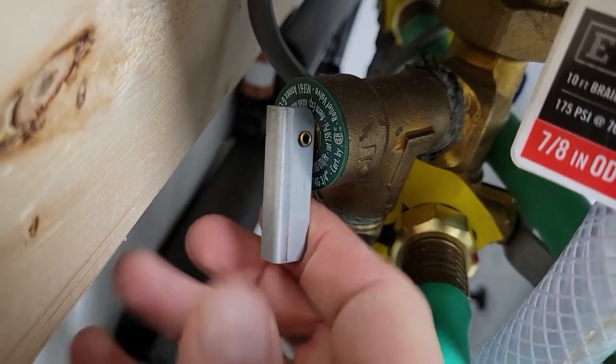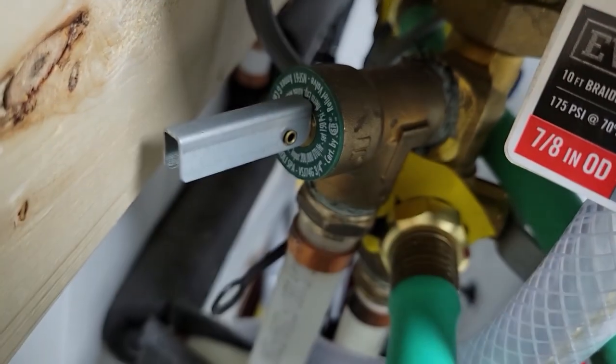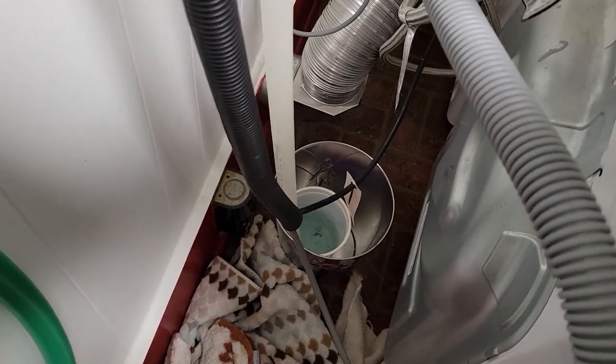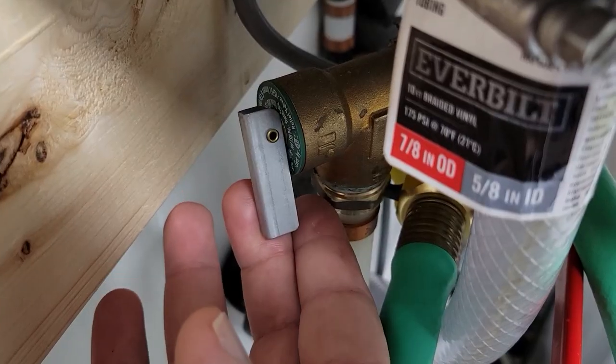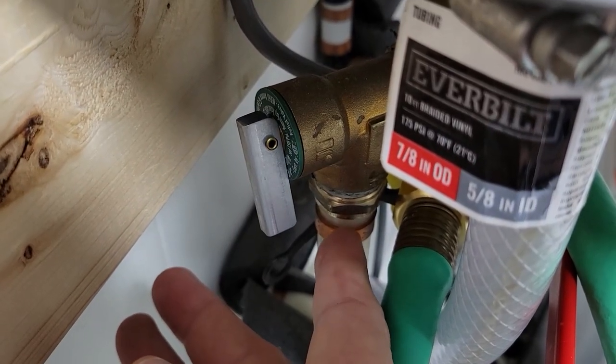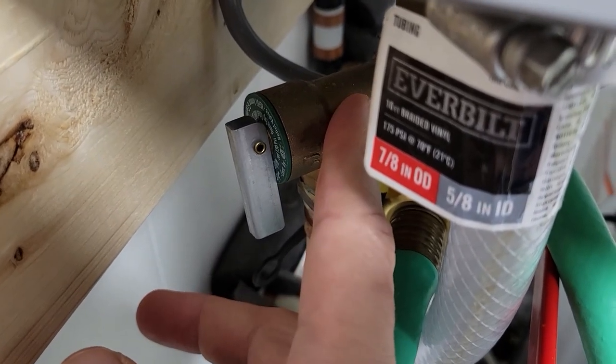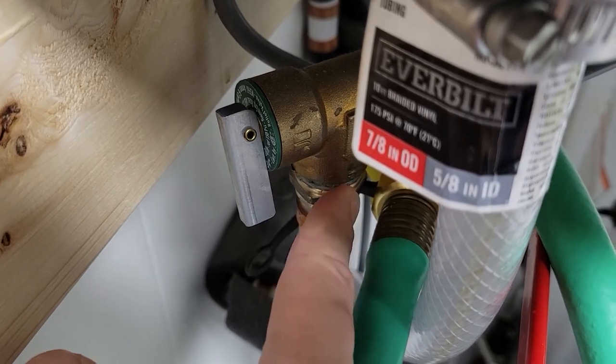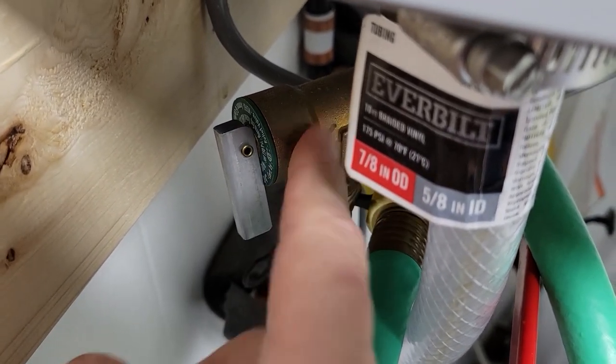This is also a good time to check your T&P (temperature and pressure) relief valve and activate it so that it flushes out — make sure the other end is going somewhere like a bucket or outdoors. If you activate the valve and no water comes out, this unit needs to be replaced. If water does come out but when you close the valve the water continues flowing, then you need to replace this valve.